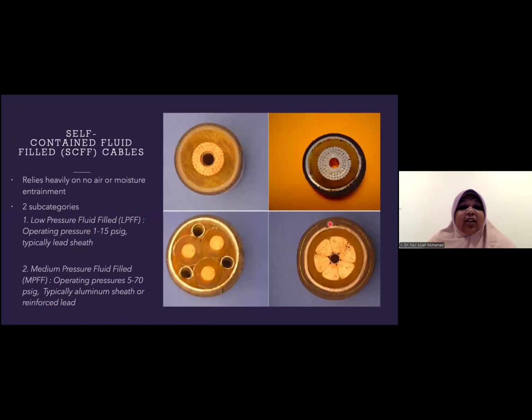Then there are a few configurations of SCFF cable. This one is three-phase. This one is also three-phase. We have one single core where the oil or gas is here, and they have paper impregnated. It depends on the power requirement. It relies heavily on no air or moisture being entrained, because moisture and air in here will degrade the cable. There are two categories: low pressure fluid filled and medium pressure fluid filled.